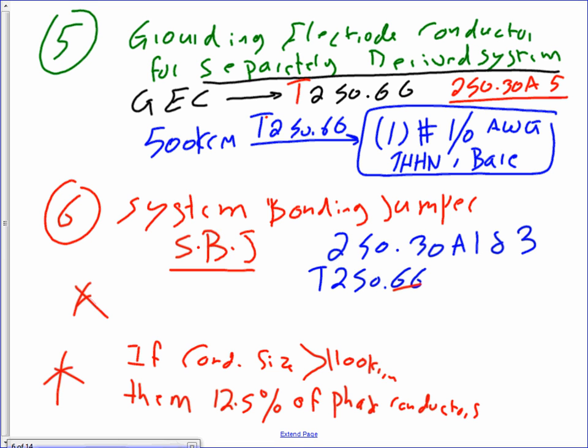Okay, the main bonding jumper. There you go. This is the one that takes the neutral and the ground bars and ties them together with a wire. They call it bonding the neutral. Main bonding jumper is at the service. For separately derived systems, guys, they call it system bonding jumper. They're all the same. One at the service and the other one is at a separately derived system. Very identical calculation for them.